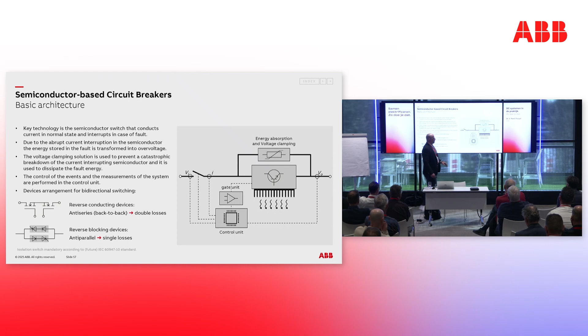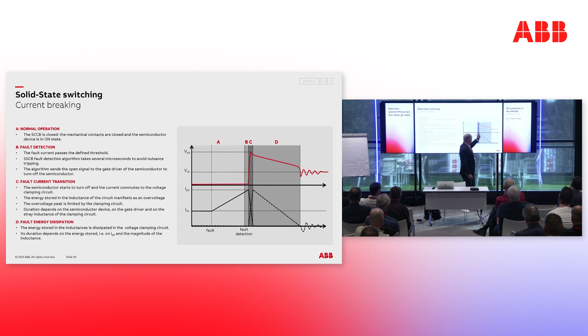And these are the waveforms of what I was describing just before. We have a current that starts rising after the fault. We hit some threshold. Then there is a time window when we don't interrupt the current. Why? Because you can have just a load disconnection, something you don't want to act upon. So every manufacturer has some time window. Everybody does it slightly differently, but it is always there. At some point, we finally decide to turn off. The current in the semiconductor goes down to zero. It is transferred to the energy clamping circuit, and that also manifests as the overvoltage. Having the high voltage across the variable resistor, essentially, and the current going to zero dissipates the energy.